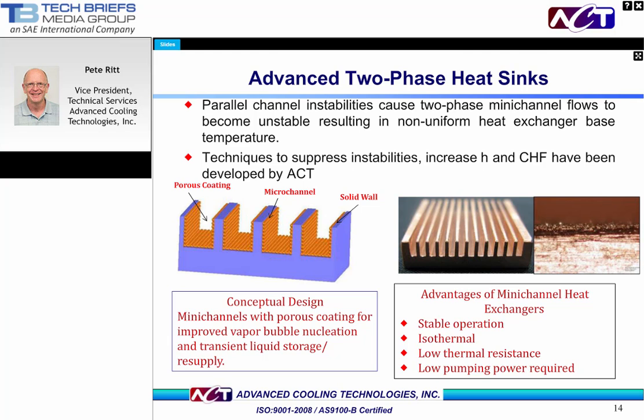In some cases, flow through parallel channels of mini-channel coolers can cause instabilities, particularly with large bubble formation that can cause severe back pressure. The bubbles can prevent flow through the channel, resulting in erratic and sometimes problematic performance. ACT, working with others, has developed a coating solution to help minimize these instabilities. The solution consists of building a microporous particle layer on the inside portion of the mini-channel structure. A concept of this can be seen on the left. The purple represents current metallic microchannel coolers, and the orange represents the microporous coating.